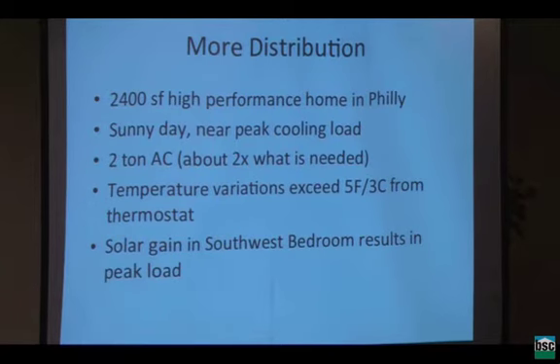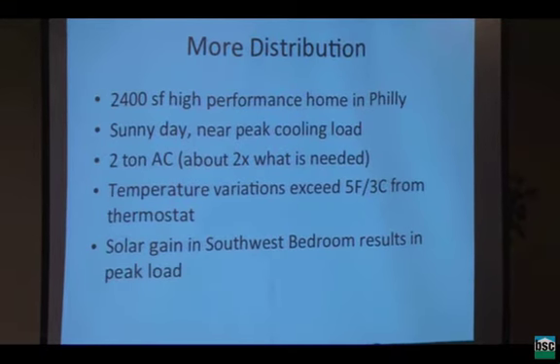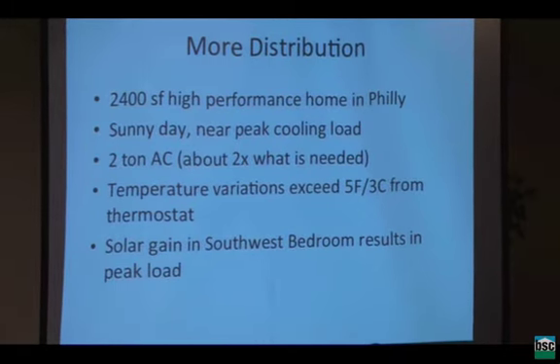This is a really well put together house by a lot of committed researcher types who wear lab coats and stuff. And they bought a 2-ton air conditioner. Why? Because that's the smallest you can get that's any efficiency, even though they needed about 1 ton. And the result is that the temperature variations exceeded 5 degrees Fahrenheit from the thermostat set point. This doesn't mean that the house is necessarily uncomfortable, and I think, Duncan, you said this is a windmill you wanted to tilt at? The need for 5 Fahrenheit?